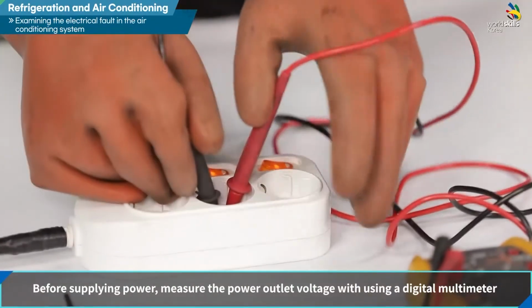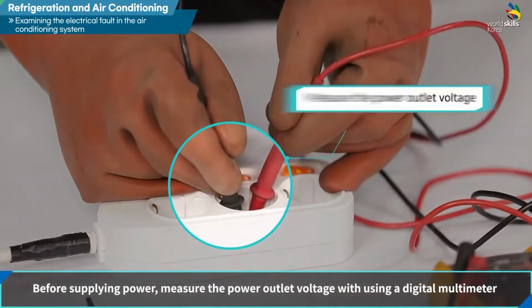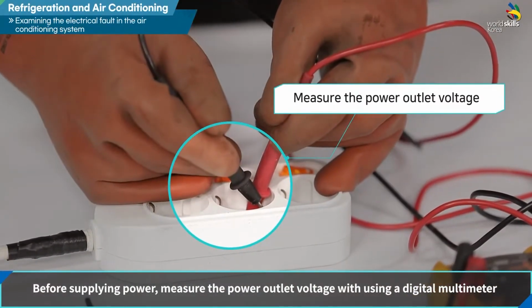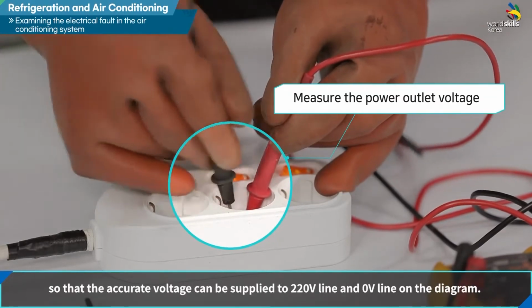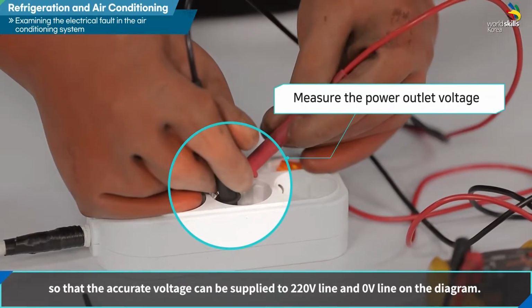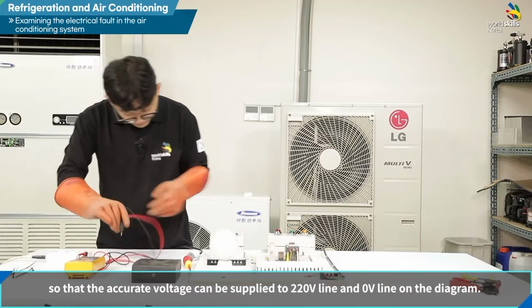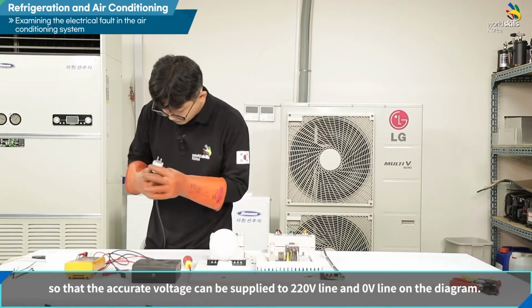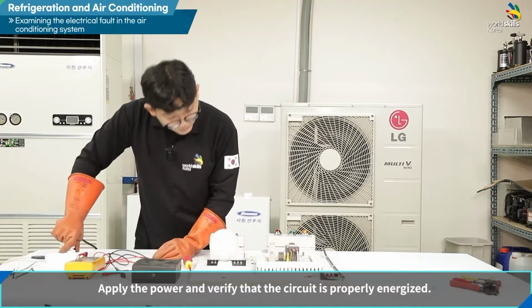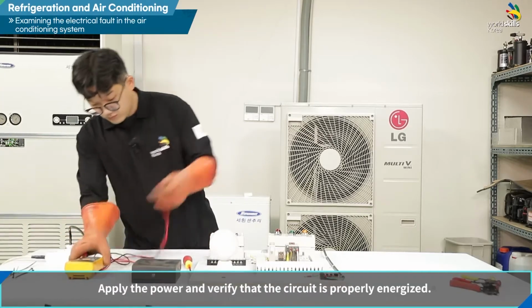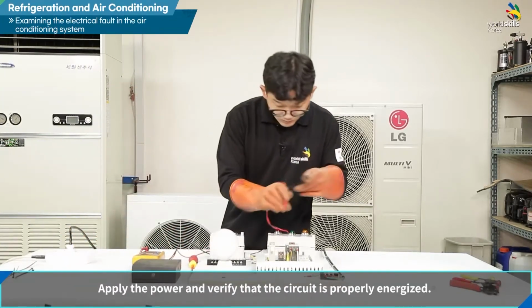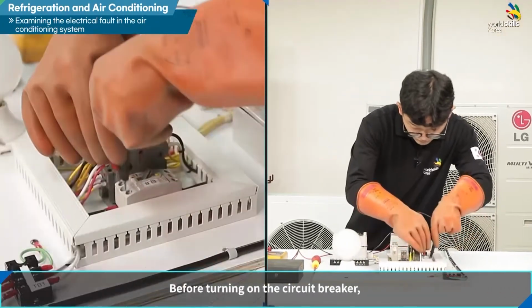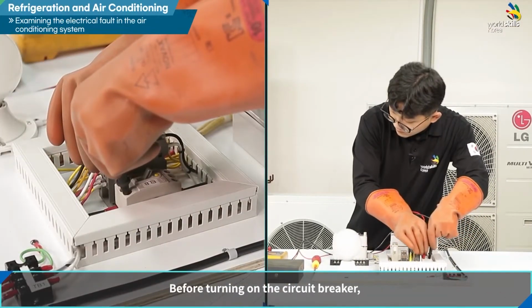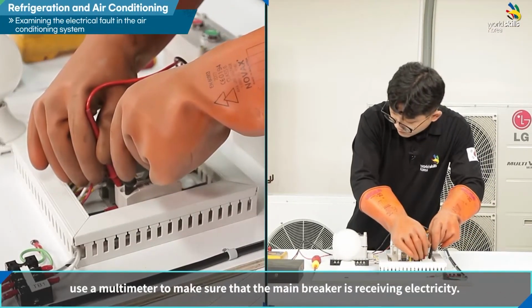Before supplying power, measure the power outlet voltage using a digital multimeter so that the accurate voltage can be supplied to the 220-volt line and 0-volt line on the diagram. Apply the power and verify that the circuit is properly energized. Before turning on the circuit breaker, use a multimeter to make sure that the main breaker is receiving electricity.